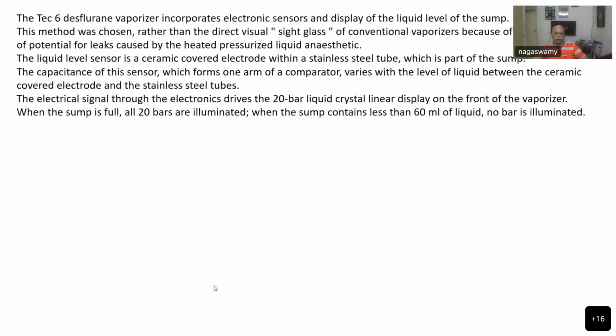And it incorporates electronic sensors and display of the liquid level in the sump. The method chosen was this rather than the visual sight glass of a conventional vaporizer, because of the possibility of potential leaks caused by the heated vaporizer liquid anesthetic. So that is why that is looking like a bar instead of the liquid level which you normally see in our other vaporizers. The liquid level sensor is a ceramic covered electrode within a stainless steel tube. This is part of the sump. So the capacitance of this sensor, which forms one arm of the comparator, varies with the level of the liquid within the ceramic covered electrode and the stainless steel tubes.